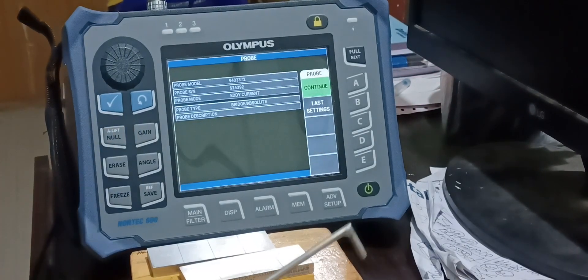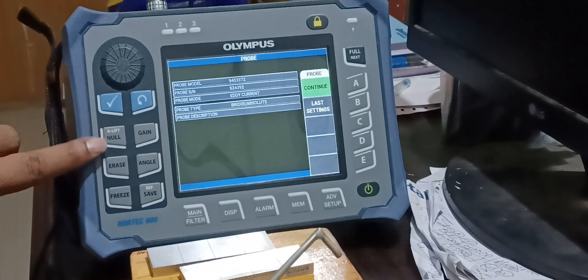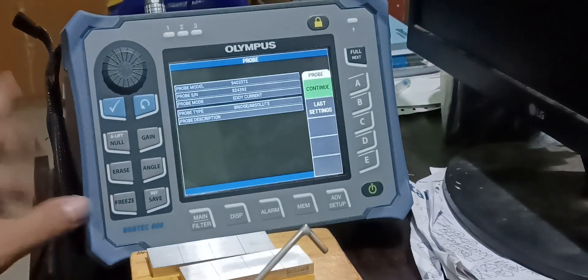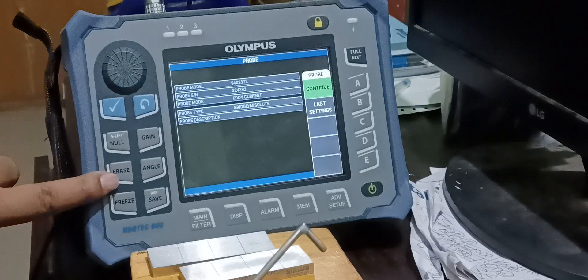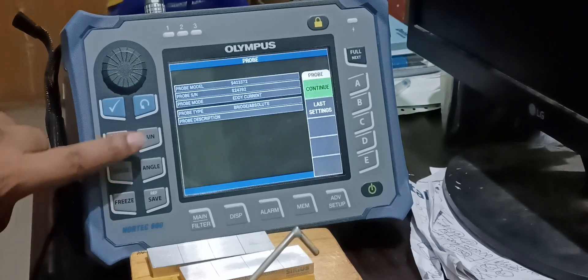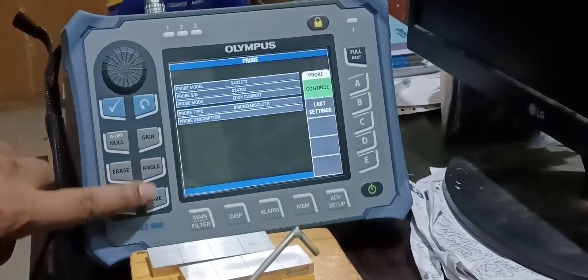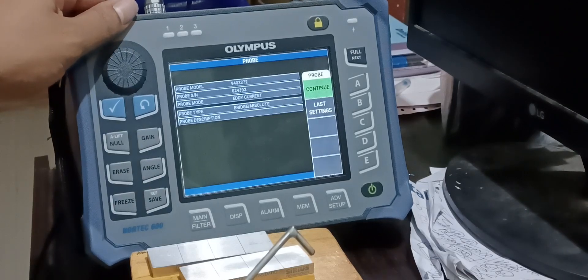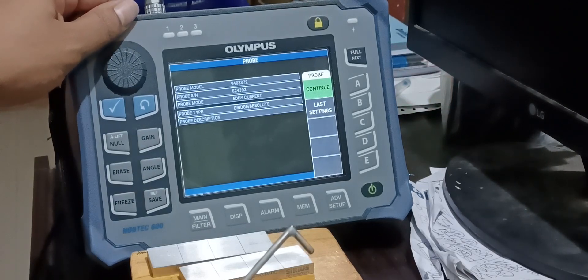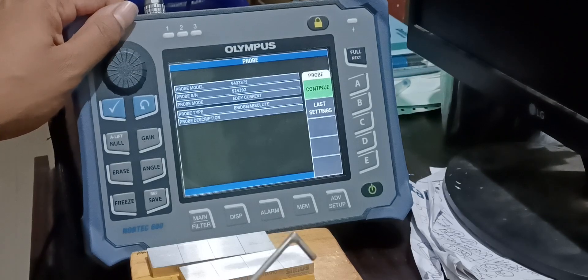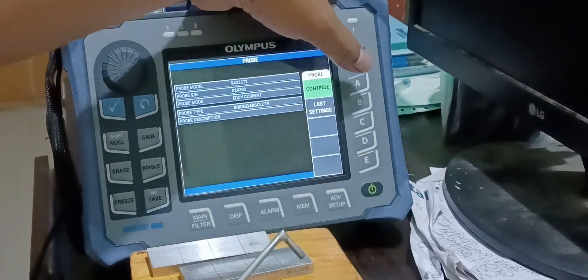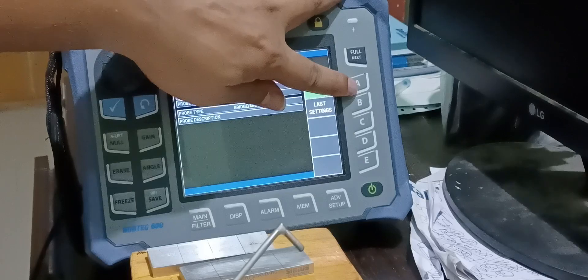Now this machine is having different menus like null, erase, freeze, gain, angle, save. The machine OEM is Olympus. The model is Nortec 600D and on the right side it has got all menus for continuing to the next options.